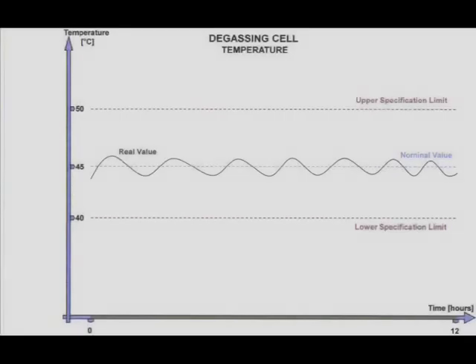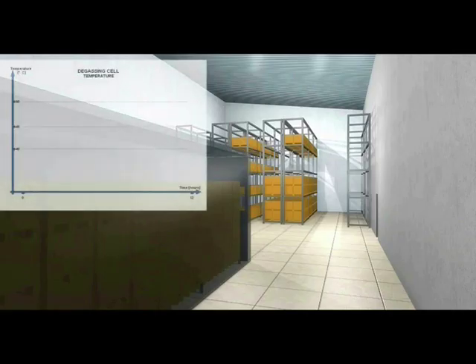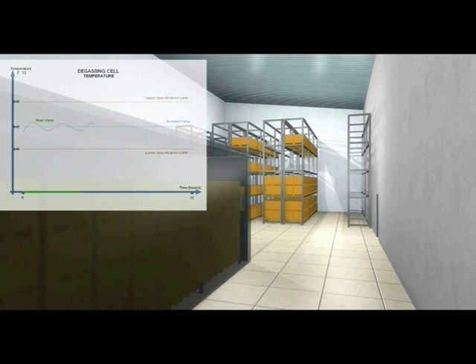The degassing cell functions in much the same way as preconditioning cell number 1 with circulated temperature-controlled air atmosphere, typically 45 degrees Celsius. The air is however constantly replaced and exhausted to the ethylene oxide neutralizing system.